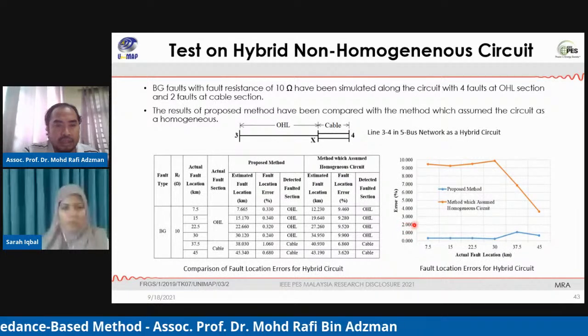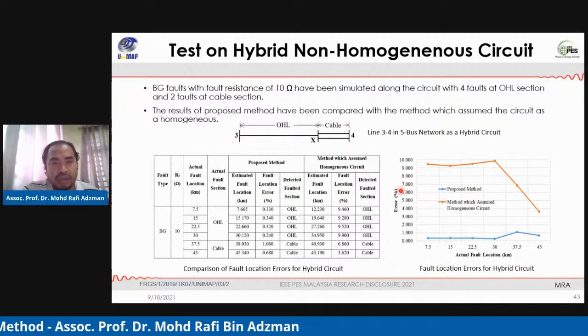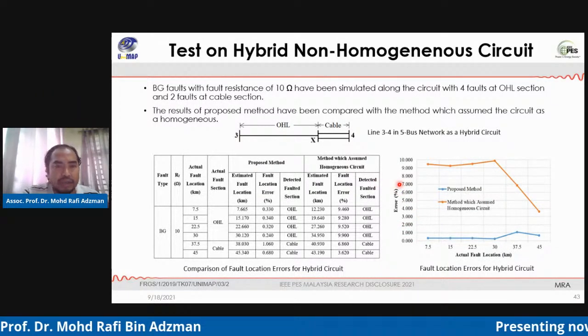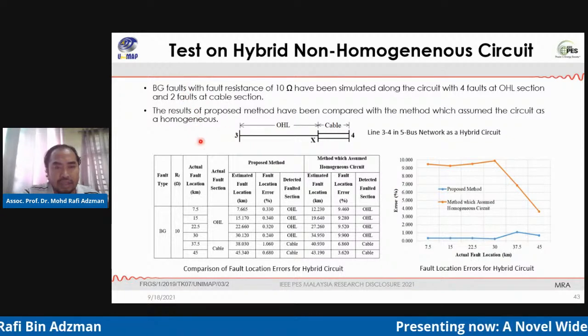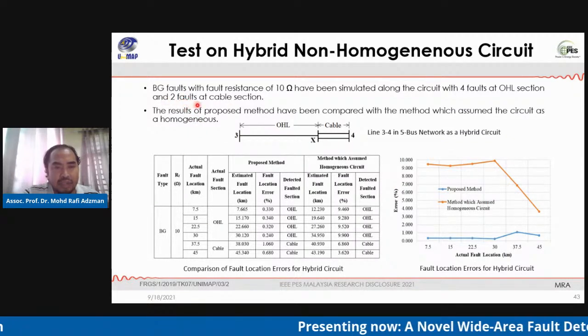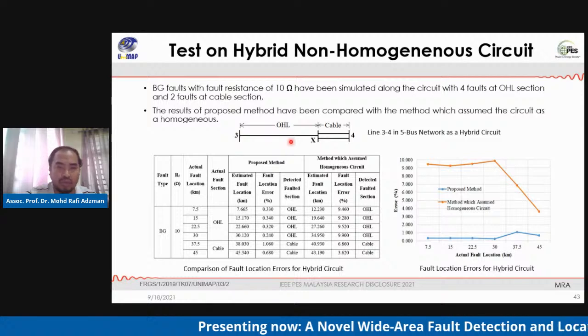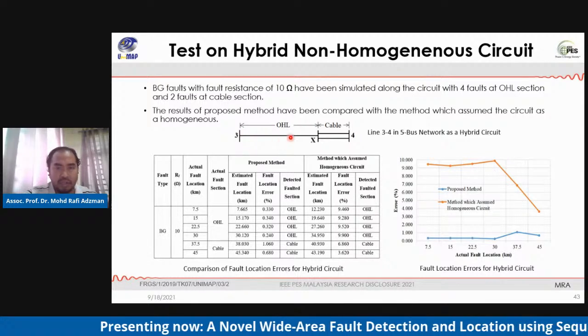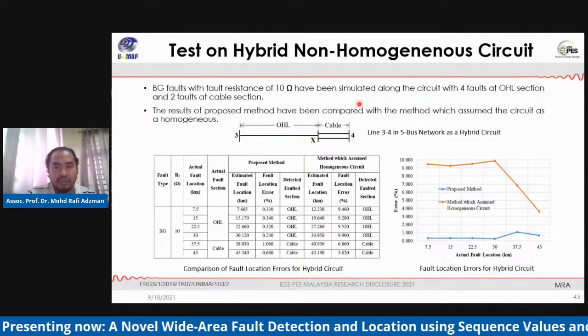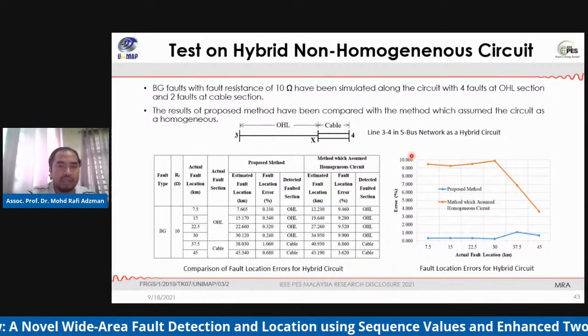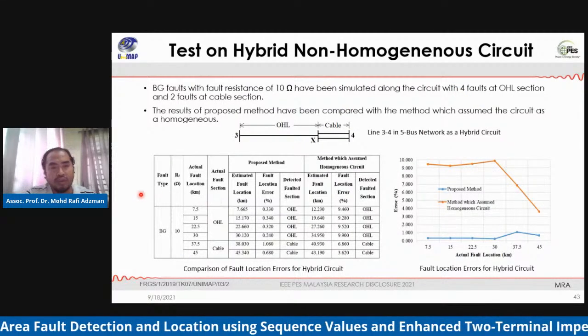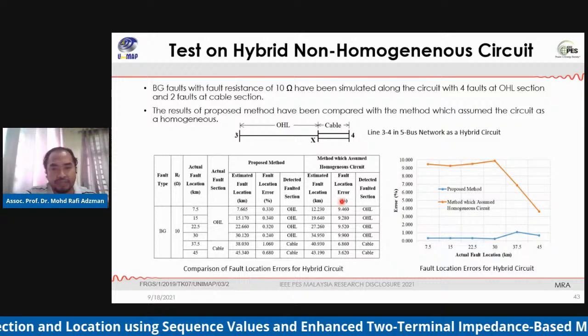So here is the result based on the hybrid non-homogeneous circuit. For this, we tested a BG fault with a fault resistance of 10 ohm. We simulated along the circuit with 4 faults at the overhead line section and 2 faults at the cable sections.